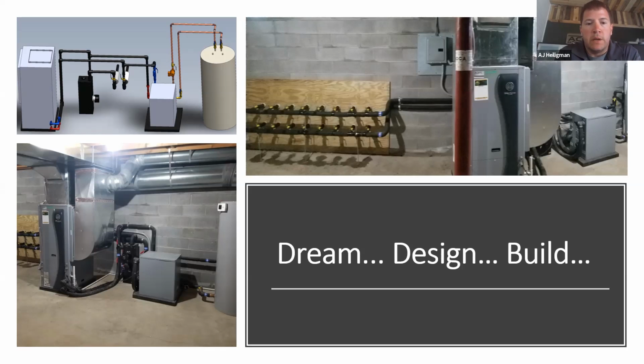Each one of those loops is an individual loop that's 600 feet long, and it goes out a trench 300 feet and then comes back in the same trench 300 feet. So he has eight pipes, 600 feet each, for a total of 4,800 linear feet of pipe buried underground. And then that gets connected to the flow center.